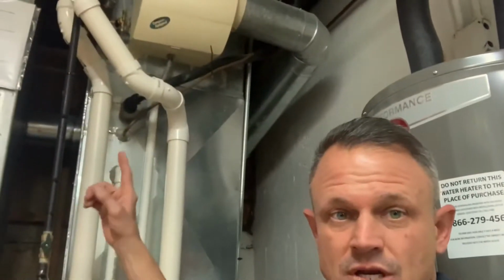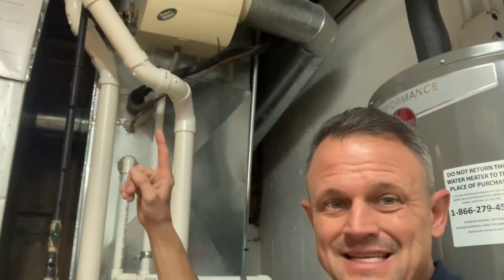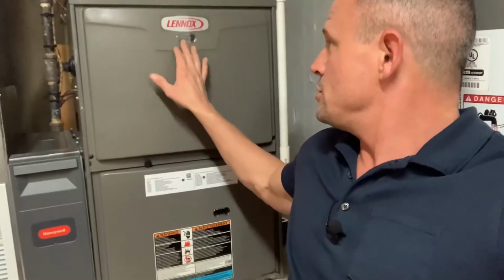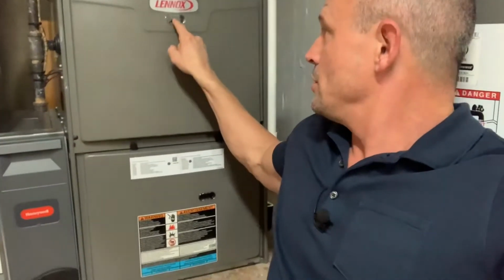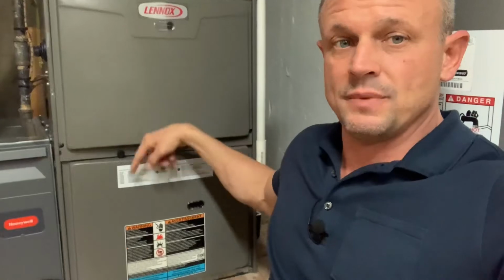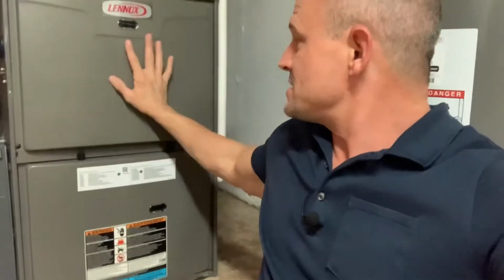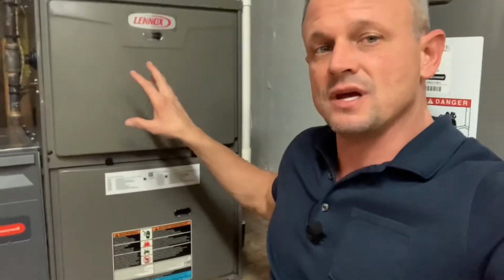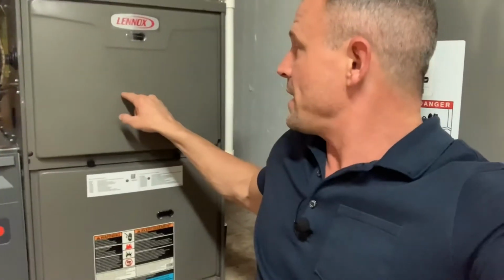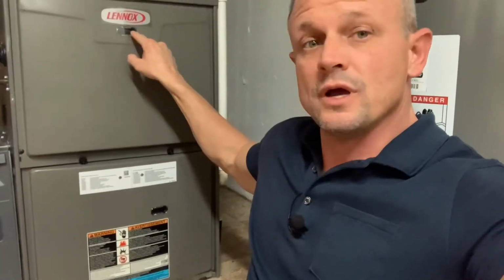And then with the air conditioning, if you look up here, you'll see these line sets, and behind this ductwork is where the evaporator coil is, and that is where it cools off and gives you that nice crisp cool air. I want you to look for these little windows. Usually they'll be on both panels. I'm going to take this off so you guys can get a visual in here, but in this upper panel, you can look through to see the burners when they're actually on. You can check for proper ignition and flame.